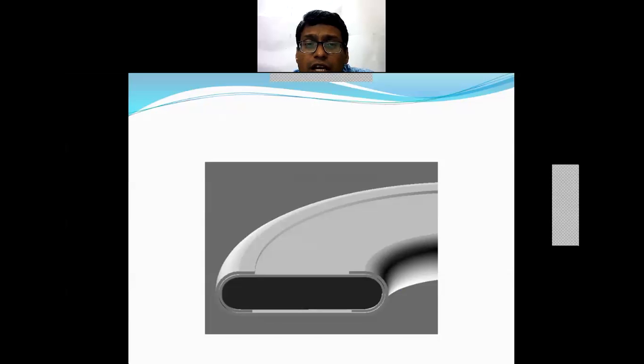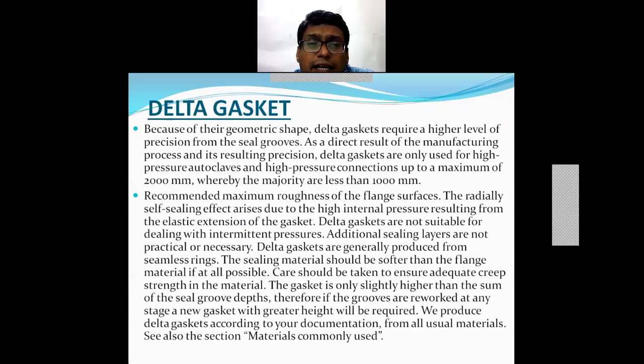So now coming to the delta gaskets. Because of their geometric shapes, these delta gaskets require the higher level of precision from the seal grooves. As the direct result from the manufacturing processes and its resulting precision, the delta gaskets are only used for high pressure autoclaves and high pressure connections up to a maximum of 2000 millimeter.